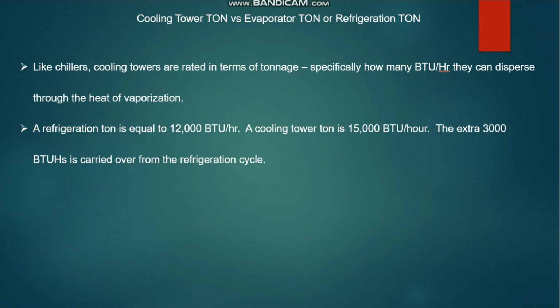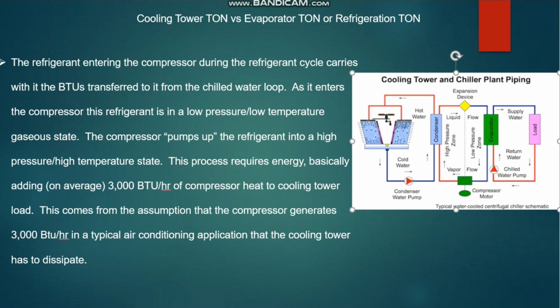And here is the important comparison between cooling tower ton of refrigeration versus evaporator ton or refrigeration ton. Like chillers, cooling towers are rated in terms of tonnage, like 1 ton, 2 ton. Specifically, how many BTU per hour they can disperse through the heat of vaporization, or we can say evaporative cooling. A refrigeration ton is equal to 12,000 BTU per hour, but a cooling tower ton is equal to 15,000 BTU per hour. This extra 3,000 BTU per hour is carried over from the refrigeration cycle. I will explain how it comes.